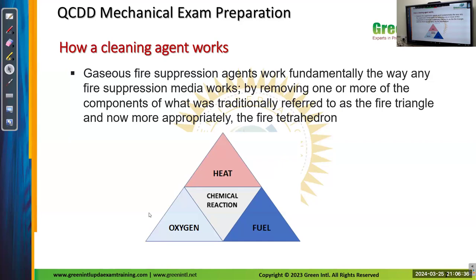So this is the one we have seen: triangle, heat, fuel, and oxygen. Gaseous fire suppression agents work fundamentally the way any fire suppression media works, by removing one or more of the components of what was traditionally referred to as the fire triangle, and now more appropriately the fire tetrahedron. This is the fire tetrahedron. So it will remove one or two. Fuel we cannot remove, right? We can remove either heat or oxygen. Fuel we cannot, because it is a material present in that area.